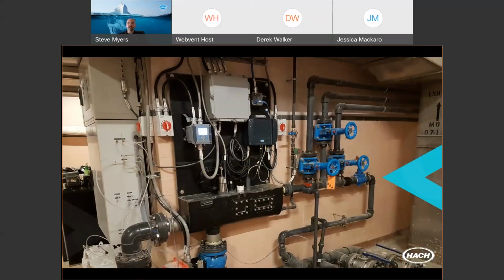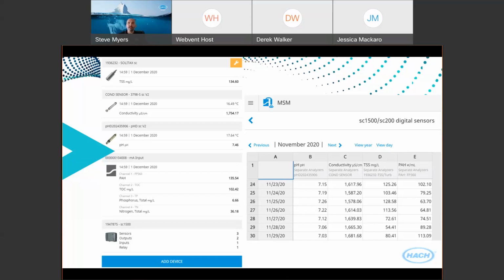...the biotector there on the left, now facing to the left, but they have this instrument trough where they now have the ability to measure suspended solids in real time, pH, conductivity, and oil in water. These all connect to one of the cloud-based control systems or controllers and provide visual input to the management of the facility, as well as real-time readings and proactive diagnostics and instrumentation health readings, essentially feeding the cloud platform. So here's an example of what that looks like, whether you're on an iPad or looking at this on your computer screen, with the ability to download some of this real-time data.